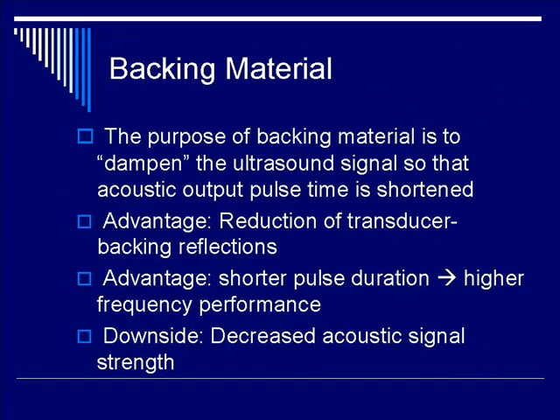Now the backing material, which we talked about in the beginning of the lecture. The purpose of the backing material is to dampen the ultrasound signal so that the acoustic output pulse time duration is shortened.